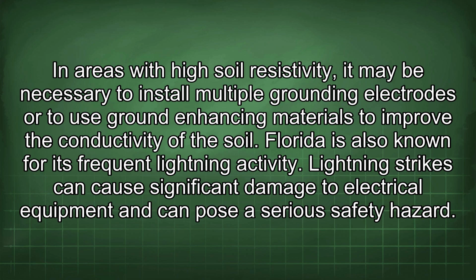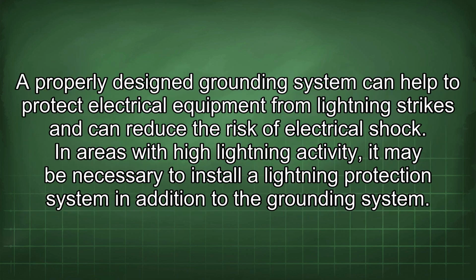Florida is also known for its frequent lightning activity. Lightning strikes can cause significant damage to electrical equipment and can pose a serious safety hazard. A properly designed grounding system can help to protect electrical equipment from lightning strikes and can reduce the risk of electrical shock.